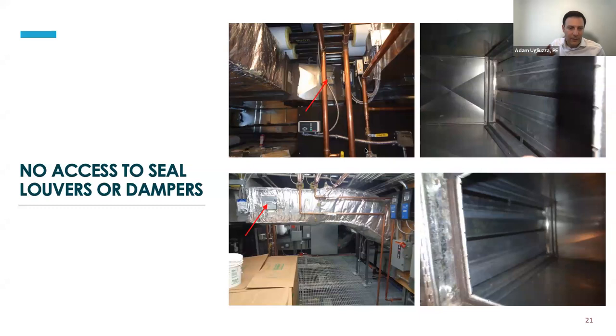Here's an example. As I mentioned, you can run it without sealing; sometimes you don't have access to seal the louver or the damper because it might be 50 feet in the air and you can't get a lift back there.